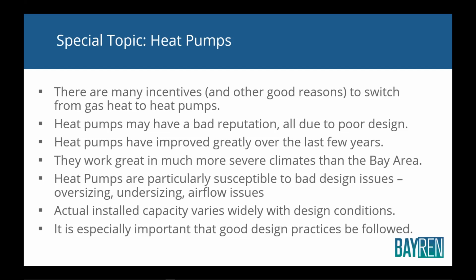I actually live over closer to Sacramento where we're up close to 100 degrees. But we have fairly mild winters. They're perfect for our climate zone. They're perfect for most of Texas, okay? The actual installed capacity varies widely based on design conditions, okay? So you do need to do a good Manual S because this heat pump in this climate zone is gonna work different than that exact same heat pump in a different climate zone, all right? It is especially important that good design practices be followed for heat pumps.